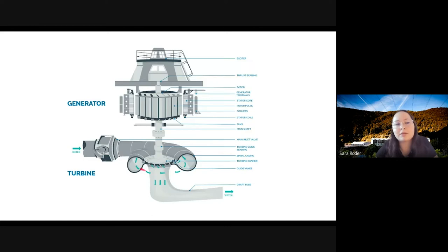And this water spins around and enters through our turbines, and most of our turbines here at Snowy Hydro are what's called Francis runners. That's the specific design and shape of them. And it means our water enters horizontally and leaves vertically through our draft tube. And our turbine there is coupled via the shaft to our generator. And I'll pass over to Beck now, who can talk about the top half of that picture, which is our generator, which is our electrical component.